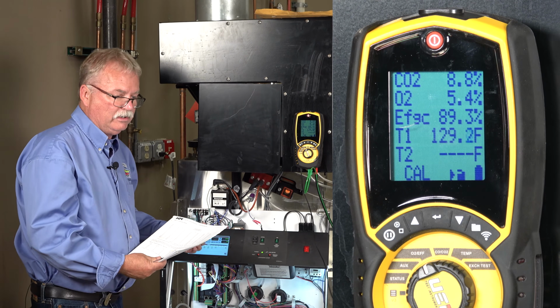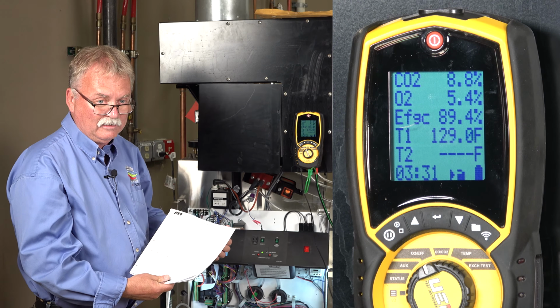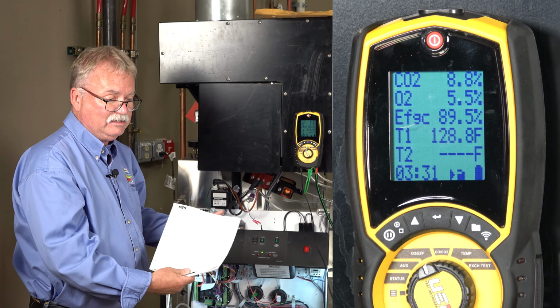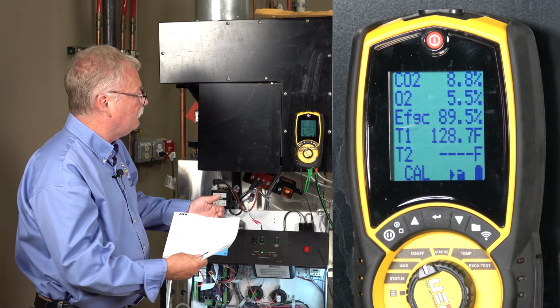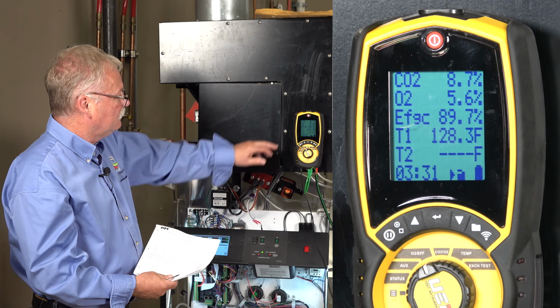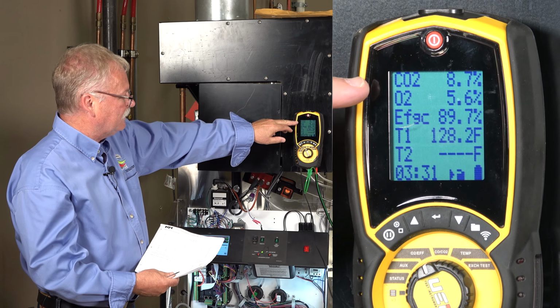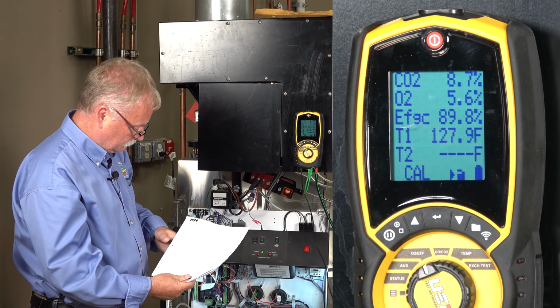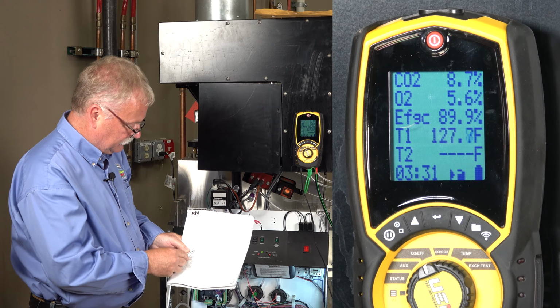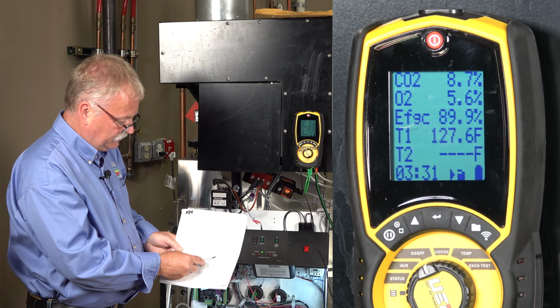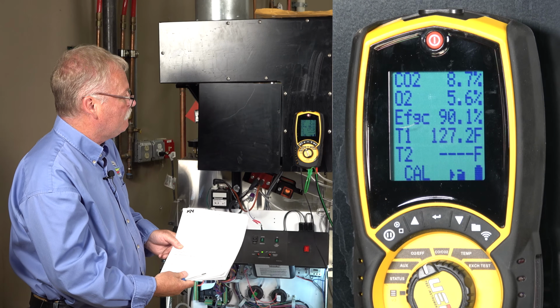Technically, this boiler is burning 125,000 BTUs right now. So that little change is going to take a while to siphon its way through the system. There we go. Right now we dropped down to 8.7. We're getting very close, with a difference of 0.2 to where we want to be.